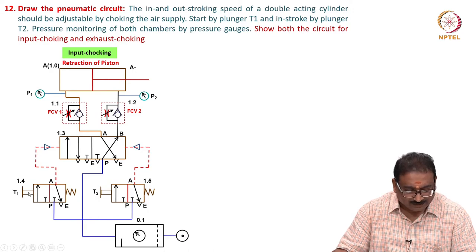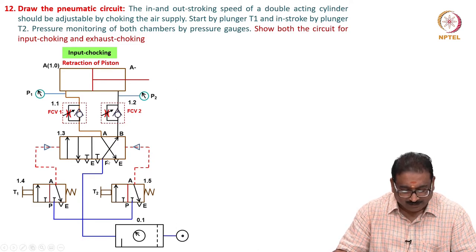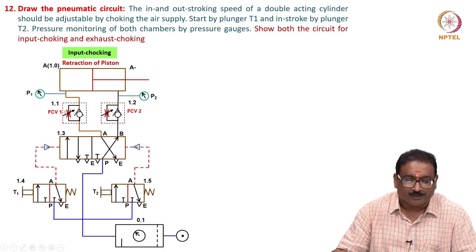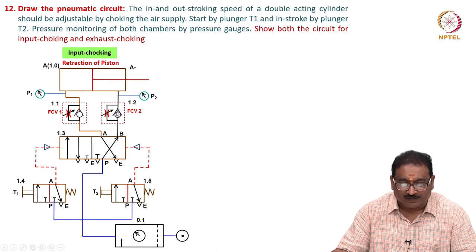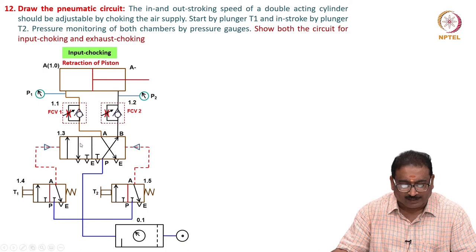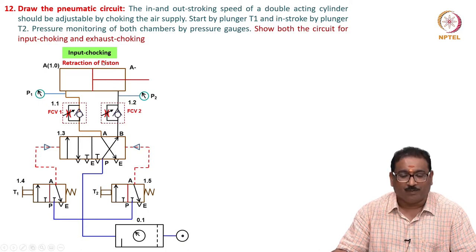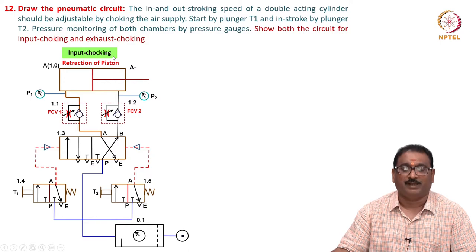For inlet choking: if you press T1, the air comes here and actuates. Then it connects here and enters. It will not pass through the check valve - it will only pass through the metered orifice to the head side. Return flow will not pass through the metered orifice - it lifts the check valve ball and goes to atmosphere. Meaning, input choking is taking place.